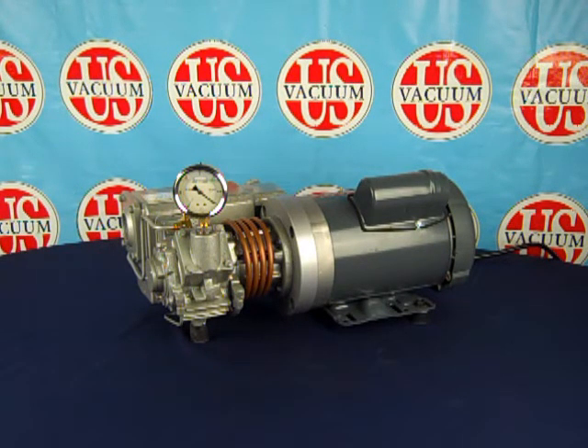Welcome to the introduction for the CPS-7D and CPS-15D Rotary Vane Vacuum Pumps. The CPS-7D and 15D are direct-drive, oil-lubricated, air-cooled Rotary Vane Vacuum Pumps capable of producing an ultimate vacuum of 2 mmHg Absolute, equivalent to roughly 99.8% full vacuum.